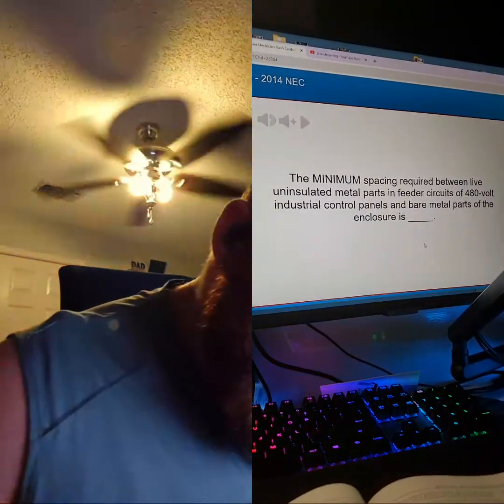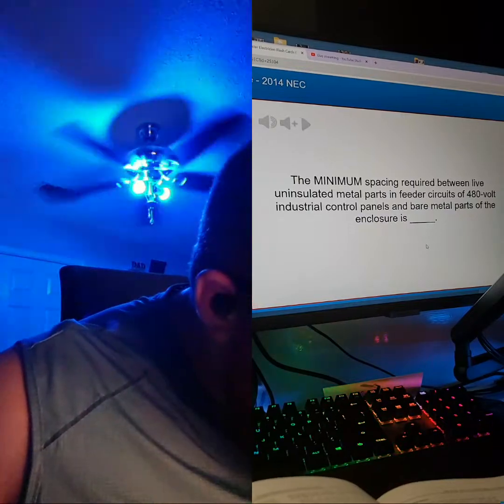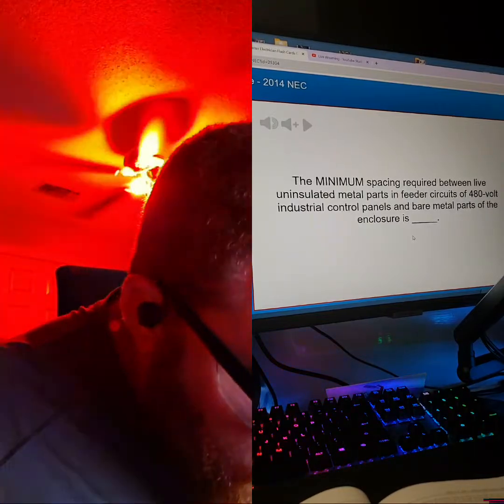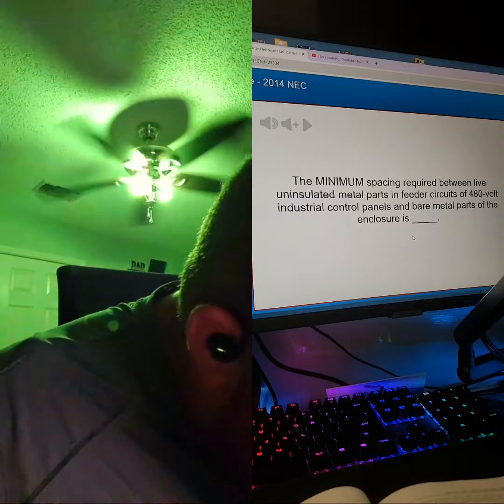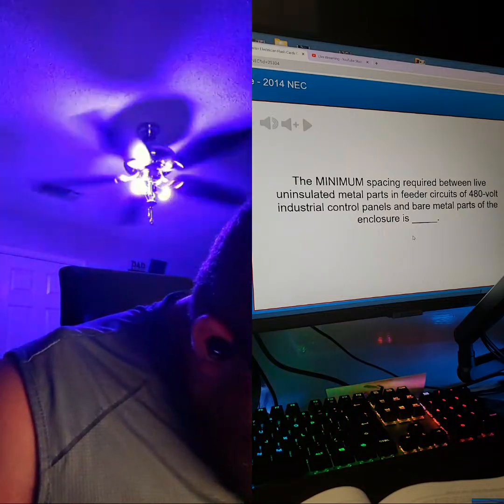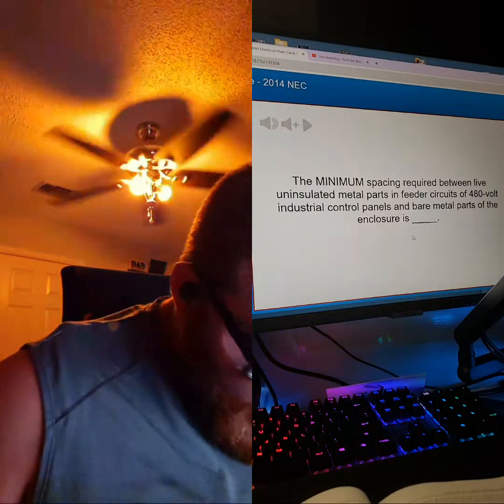430.97(D). 408.56. 430.97(D). Could be, it's the '14 code. I'm going to check it. Okay, we're right. Spacings shall not be less than. Not over 600 volts is 1 inch, live parts to ground. There you go. Is that in the table, looking from bus bar to bus bar? That would be 2.